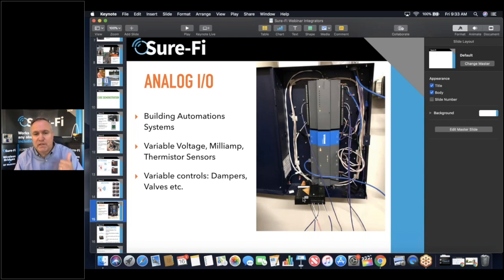This particular one was doing a light meter up on the roof. When we first connected this light meter, this unit will actually do up to 6 sensors, so you can do 2 voltage, 2 milliamp, and 2 thermistor into this unit. This was connected to a light meter. We had it on a thermistor. We had 3 there. I think it was light meter, thermistor, and occupied sensor, something like that. They were sending all 3 of those sensors wirelessly from the other side of the warehouse, because they didn't have the wire for it, and sending it over here, connecting right into the JACE unit hardwired.